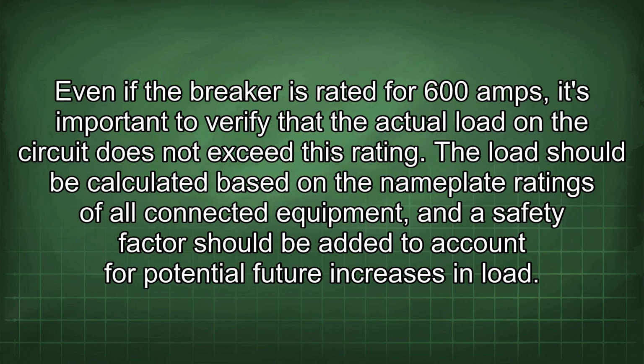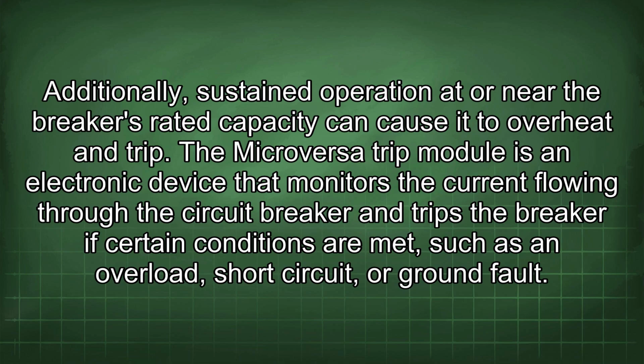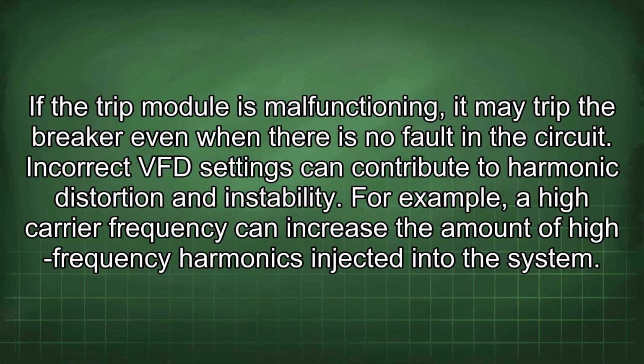Even if the breaker is rated for 600 amps, it's important to verify that the actual load in the circuit does not exceed this rating. The load should be calculated based on the nameplate ratings of all connected equipment, and a safety factor should be added to account for potential future increases in load. Additionally, sustained operation at or near the breaker's rated capacity can cause it to overheat and trip. The Microversa trip module is an electronic device that monitors the current flowing through the circuit breaker and trips the breaker if certain conditions are met, such as an overload, short circuit, or ground fault. If the trip module is malfunctioning, it may trip the breaker even when there is no fault in the circuit.